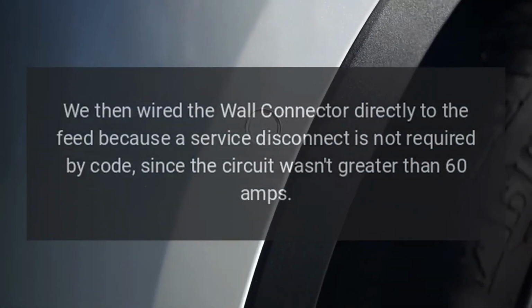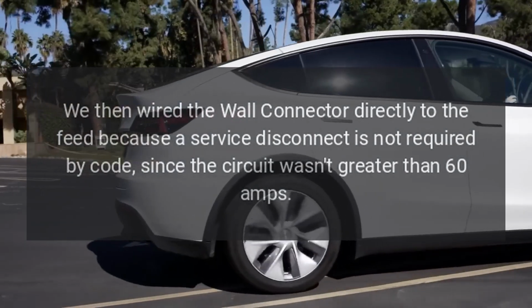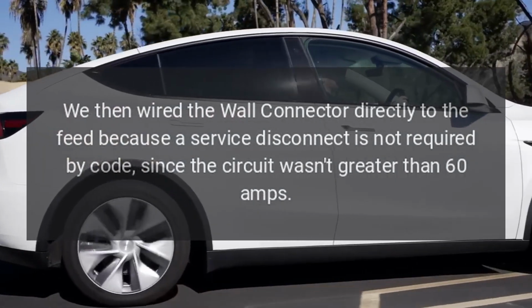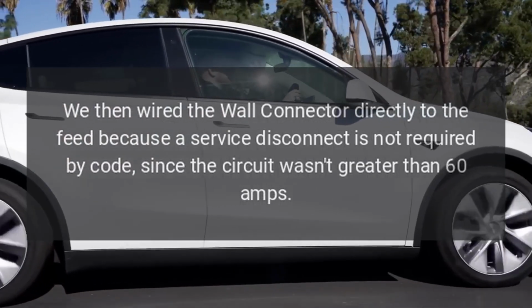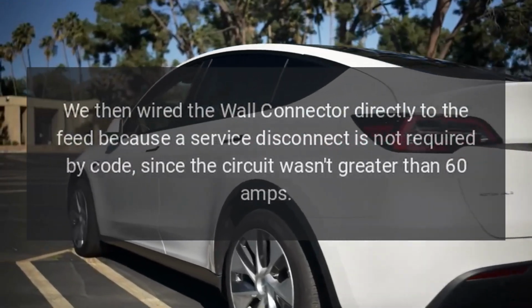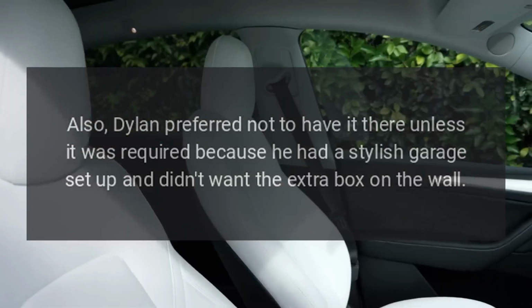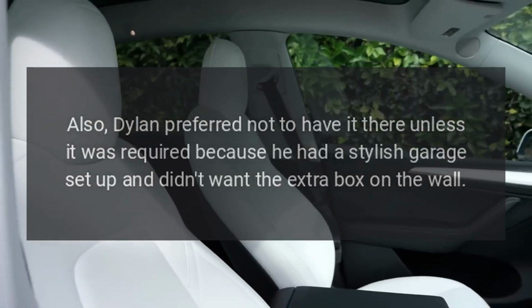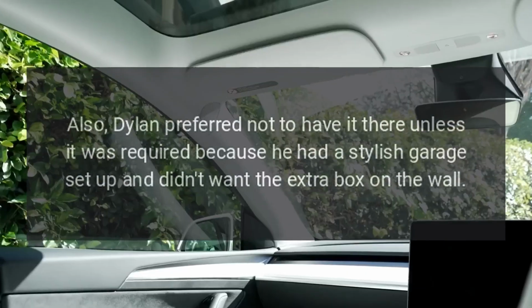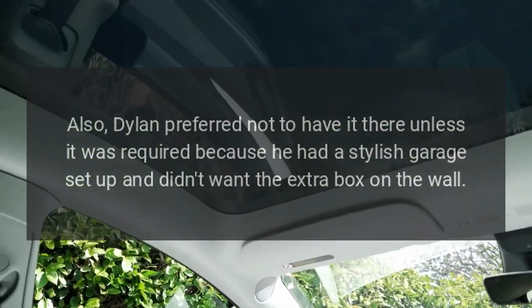We then wired the wall connector directly to the feed because a service disconnect is not required by code, since the circuit wasn't greater than 60 amps. Also, Dylan preferred not to have it there unless it was required because he had a stylish garage set up and didn't want the extra box on the wall.